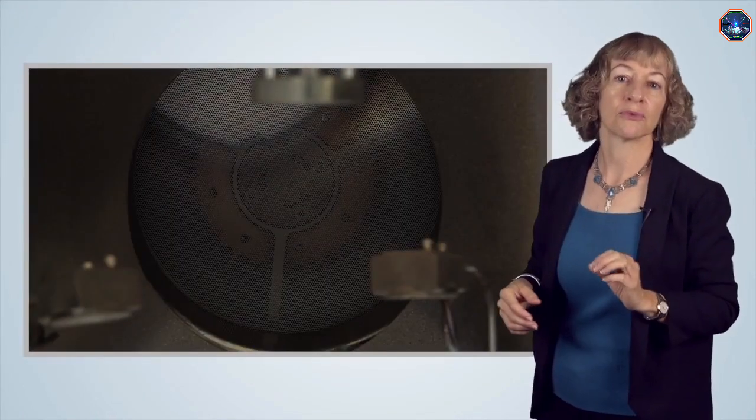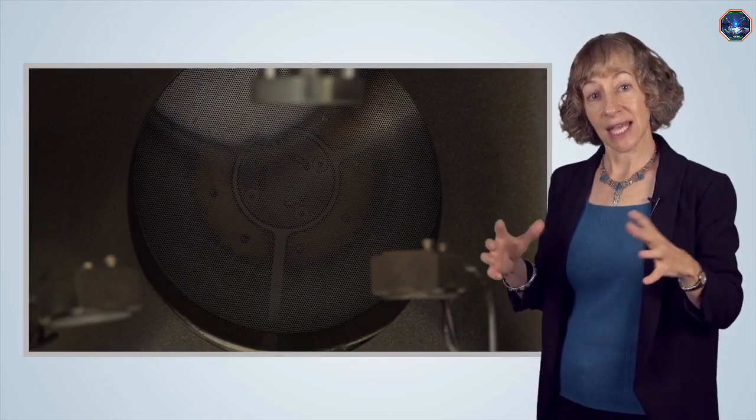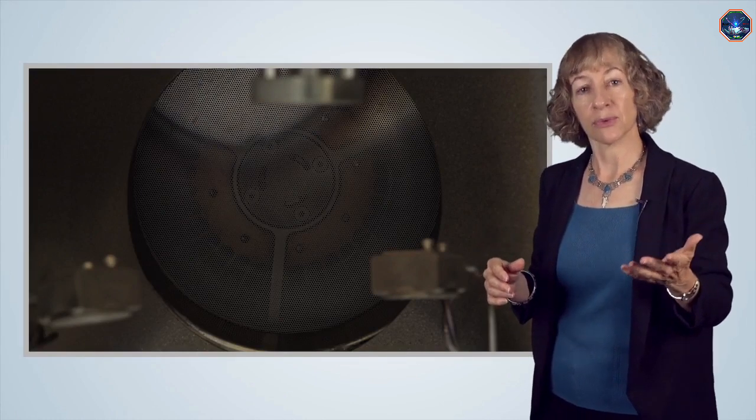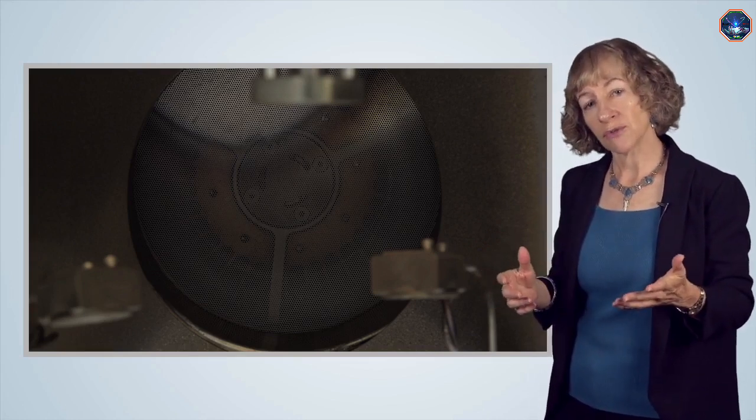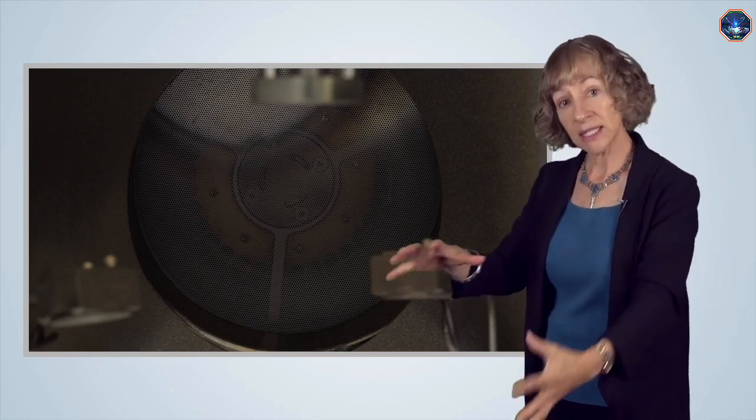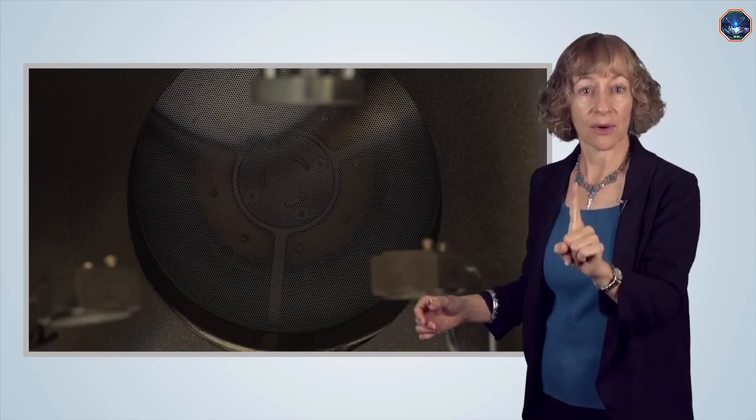A turbo pump can routinely evacuate a large vacuum chamber to 10 to the minus 7 torr, or equivalently 1.3 times 10 to the minus 5 pascals. Pressures on the order of 10 to the minus 6 torr are fine for most thin film depositions, and a correctly sized turbo pump will pump out a chamber in about one hour.